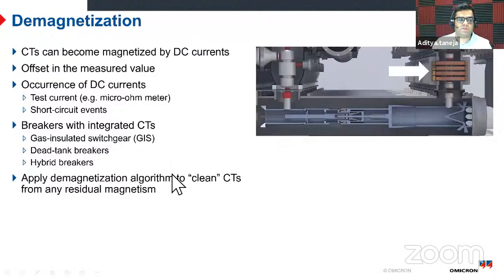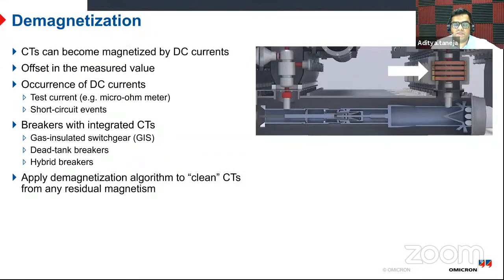So there is a solution which is available to clean this CT residual magnetism: injecting a pulsating current in the primary circuit, which will clean or reduce the residual magnetism, because otherwise this will give a false indication or it may lead to maloperation in differential protection. So yeah, it is better if it can be cleaned. So that's something which we need to take care of when we are doing these tests again, to make them non-invasive, to not open any circuit or open the CT secondary. Better to do it with the primary circuit itself. So that's all related to timing and GIS.